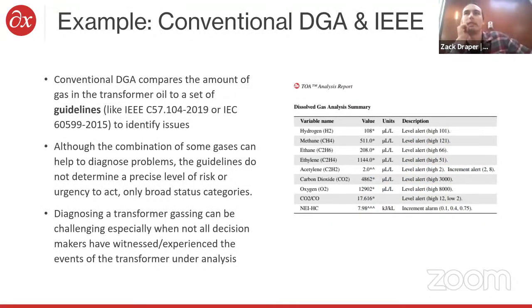So an example in conventional DGA, or what I refer to as conventional DGA, is you take gas measurements from the lab and you compare them against guidelines like IEEE or IEC. And those guidelines were established by basically saying, take a large database of gas values and figure out what the 90th percentiles are on that database of gas values. So it tells you how unusual a particular measurement is, but it doesn't give you a precise understanding of what the risk involved is in seeing that level of gas or that rate of change in gas.